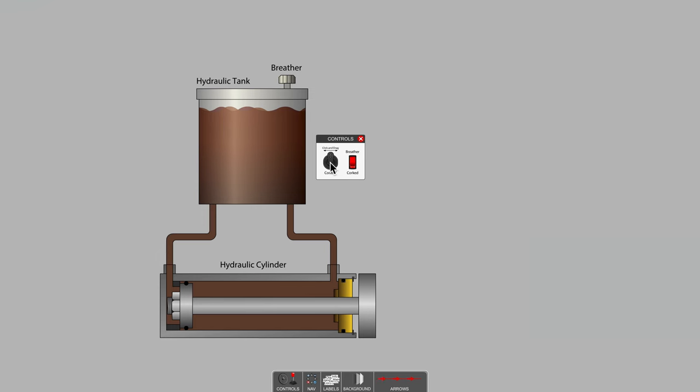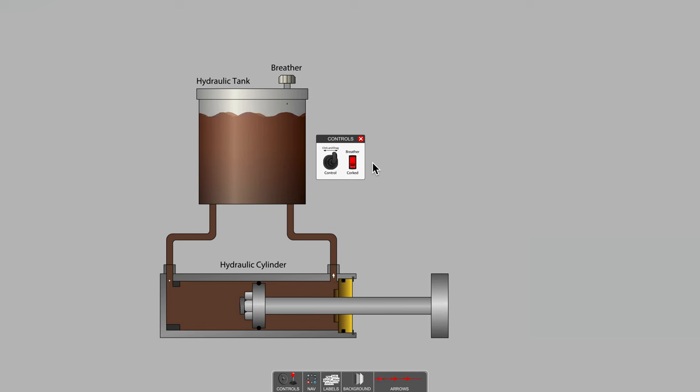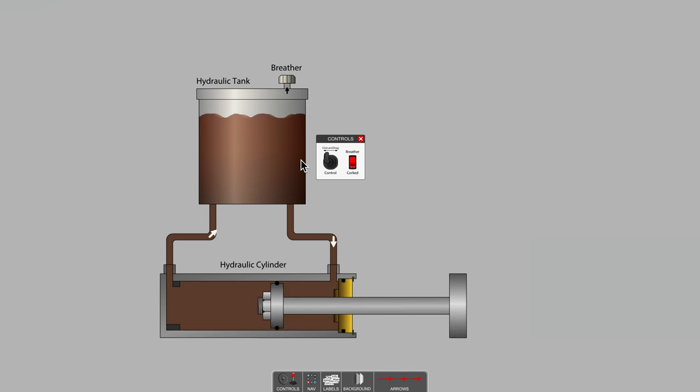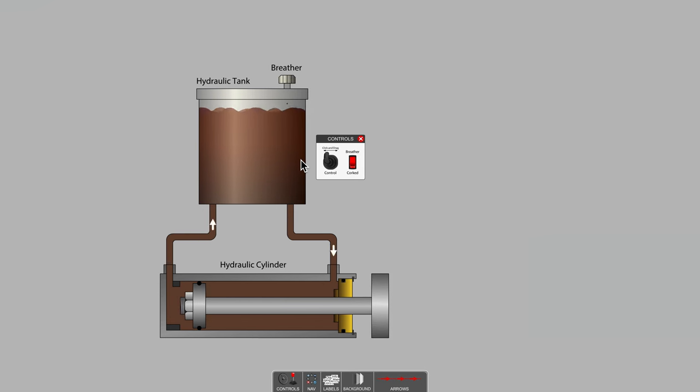One of the key points to remember if you're maintaining hydraulic systems is never to fill the tank to the level that might be marked on the tank when the cylinders are extended, as you may then overfill the tank. And when you retract the cylinder, have a bit of a spill occur right out the top through the breather.